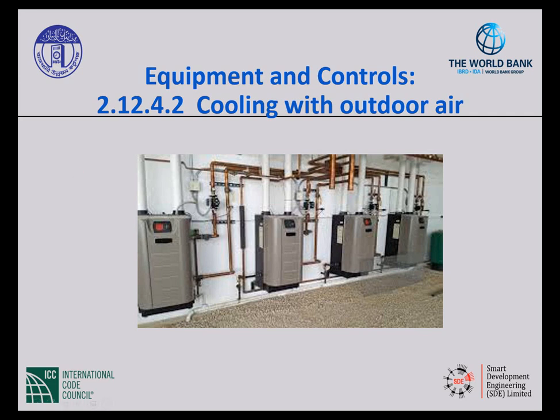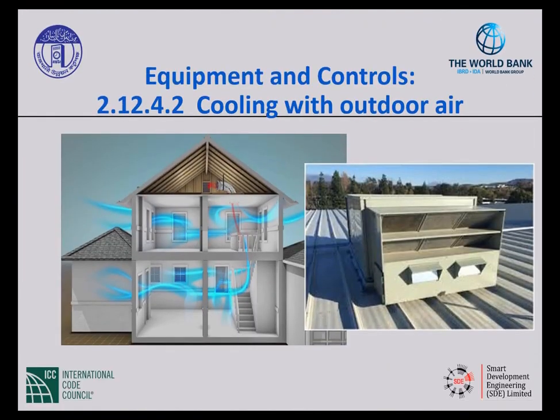All right, now we're going to talk about cooling with outside air in 212.4.2. This is telling us that each air handling system has to have the facility to use up to and including 100% of the air handling system capacity for cooling with outdoor air, and to do it automatically whenever the outdoor air will result in a lower usage of energy than would be required under normal operations of the air handling system.